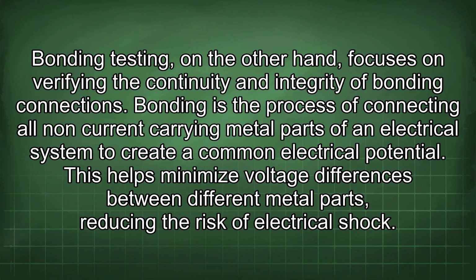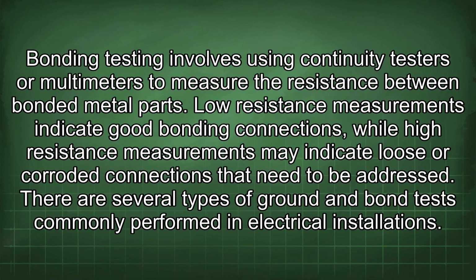This helps minimize voltage differences between different metal parts, reducing the risk of electrical shock. Bonding testing involves using continuity testers or multimeters to measure the resistance between bonded metal parts. Low resistance measurements indicate good bonding connections, while higher resistance measurements may indicate loose or corroded connections that need to be addressed. There are several types of ground and bond tests commonly performed in electrical installations.